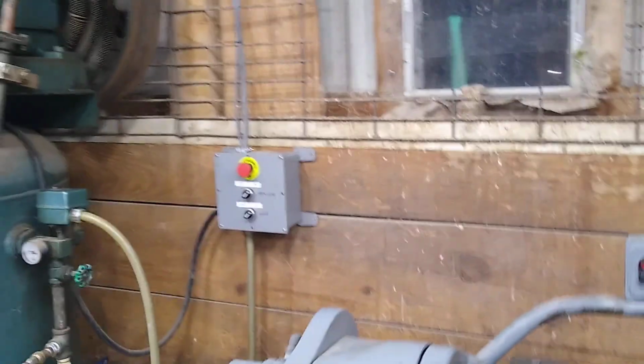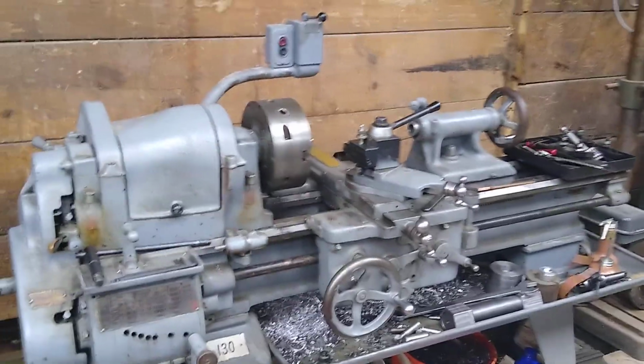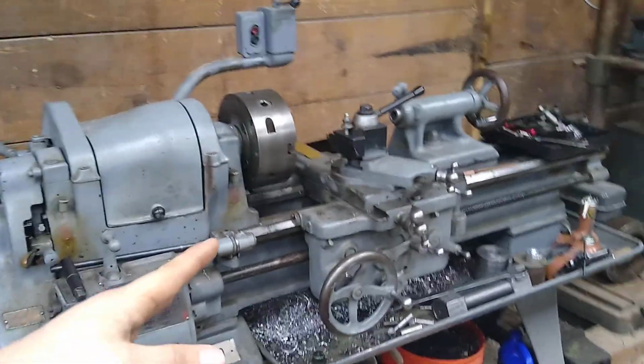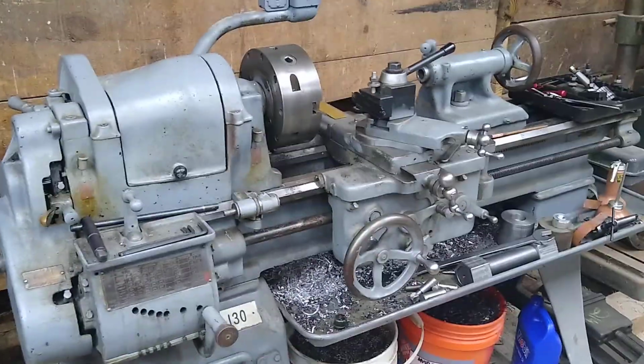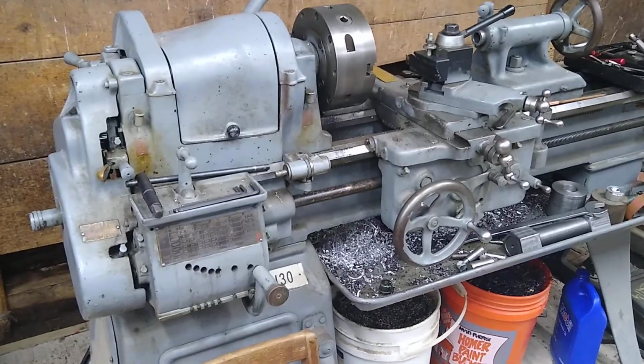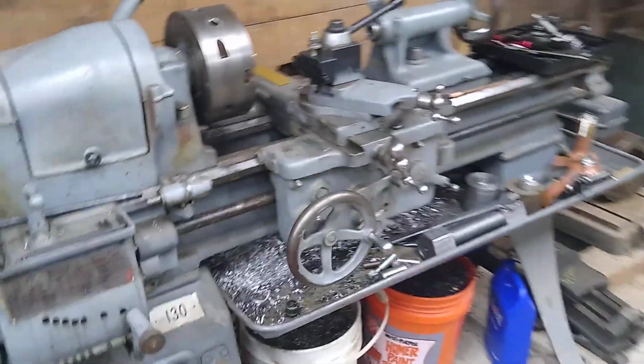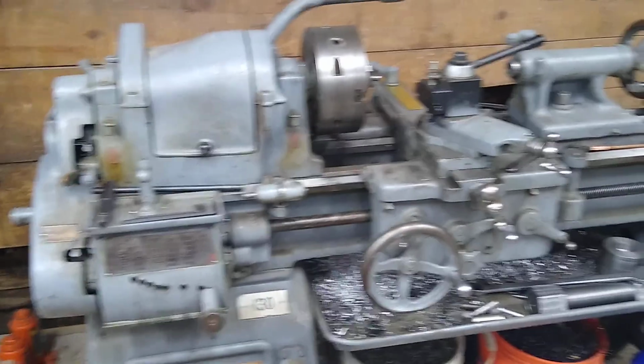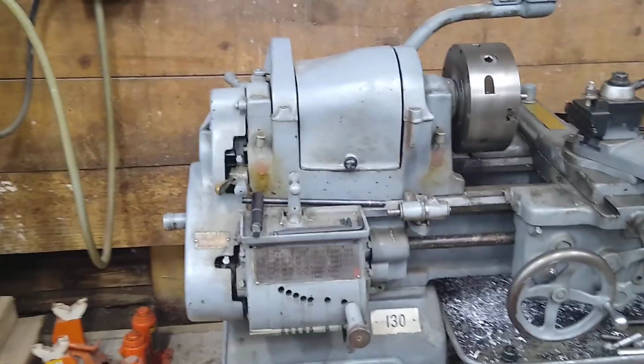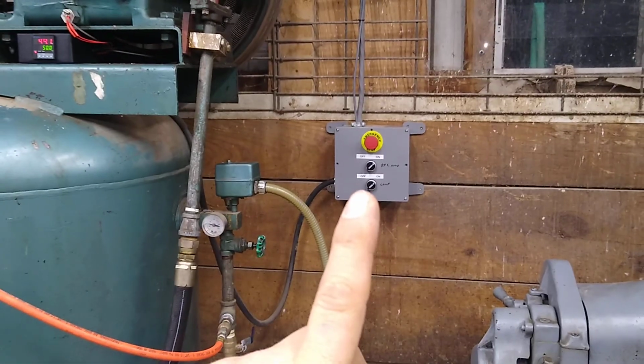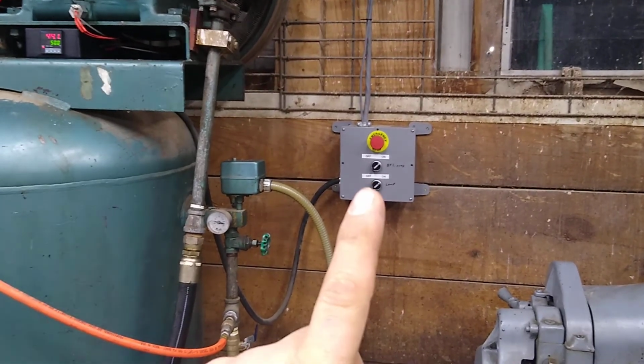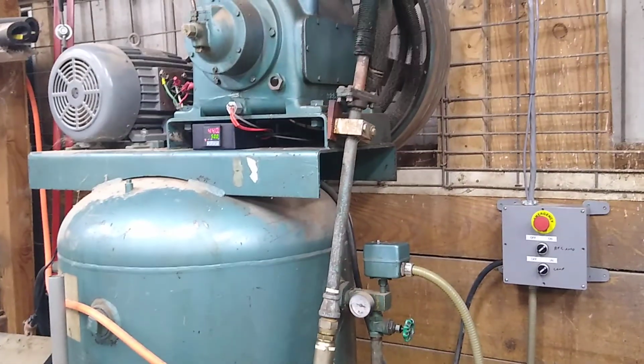That was the other thing too, I was limping along on the rotary phase converter. Every motor has a different current, so if I wanted to use it and not overamp the motor, I had to set the current maximum to whatever that motor was rated for. It was really not happy with the motor starters, they'd chatter and get real hot. I actually burned out 2 transformers for this air compressor, I was trying to run it and wasn't happy, so I burned out 2 of these little transformers.